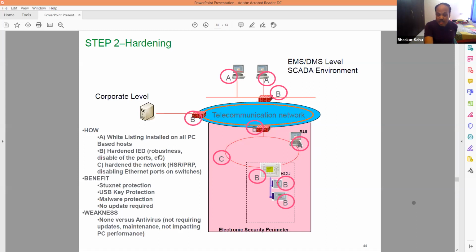Then hardening is basically robustness—meaning the relay that is supposed to perform a protection operation will perform that protection operation, and even if junk data comes in through the Ethernet port, it will not alter its operation.